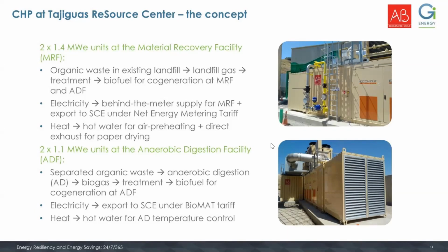The exhaust gases are fed directly to a paper drying process, so the recycled paper is dried and gains additional value, meaning it can be sold for a better price. The heat from the hot water loop of the cogen unit is used to preheat air that mixes with the exhaust going into the paper drying system. Essentially, the customer saves on burner tip fuel that would otherwise be needed to preheat the larger volume of incoming air for the paper drying process.